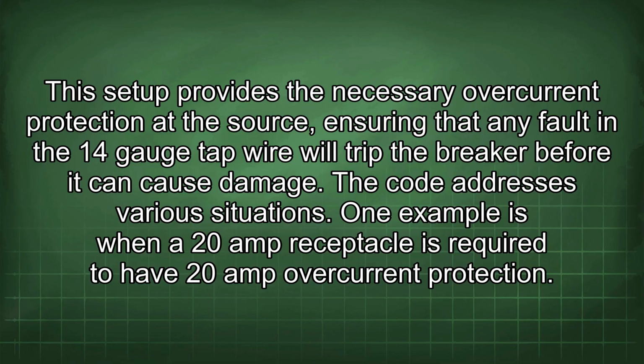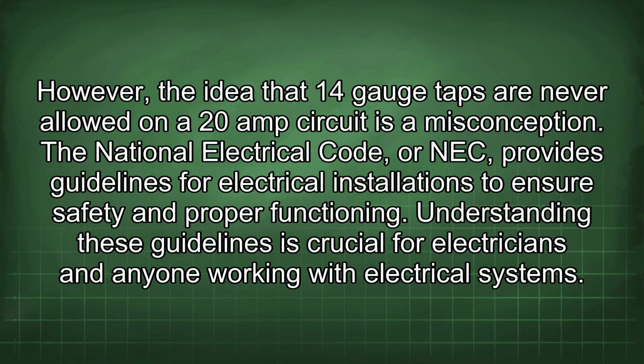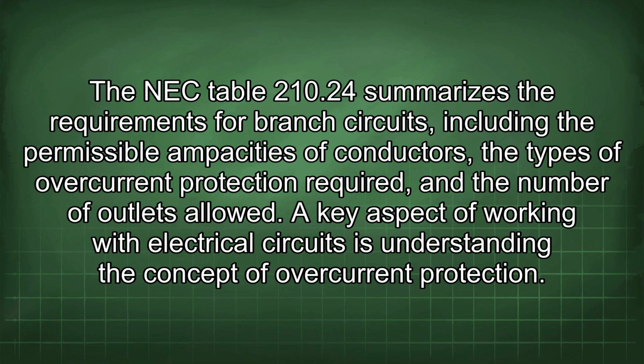The code addresses various situations. One example is when a 20-amp receptacle is required to have 20-amp overcurrent protection. However, the idea that 14-gauge taps are never allowed on a 20-amp circuit is a misconception. The National Electrical Code, or NEC, provides guidelines for electrical installations to ensure safety and proper functioning. Understanding these guidelines is crucial for electricians and anyone working with electrical systems. The NEC Table 210.24 summarizes the requirements for branch circuits, including the permissible ampacities of conductors, the types of overcurrent protection required, and the number of outlets allowed.